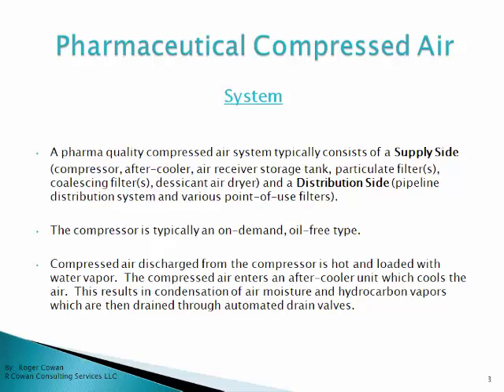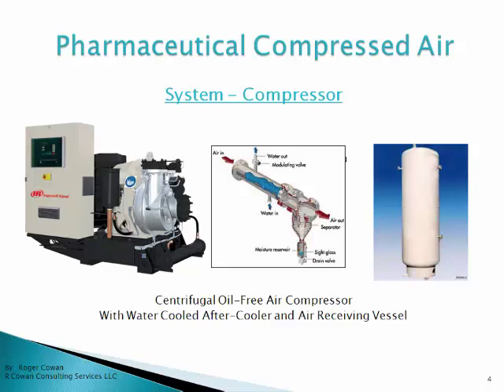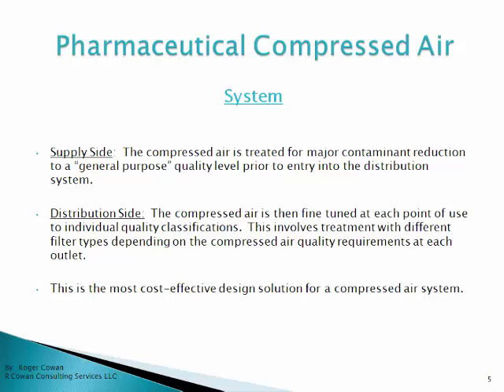Here are some diagrams and photographs of these components. On the left-hand side is a photograph of a centrifugal oil-free air compressor, typically used in pharmaceuticals. In the middle is a diagram — a cross-section of a water-cooled after cooler, which comes after the compressor. You can see the air goes in at the upper left, through a heat exchange unit with cold water going in and out, resulting in condensation of humidity that drains out through the bottom through the moisture reservoir, and then the drier air comes out through the right. On the right-hand side is a photograph of a receiving vessel.